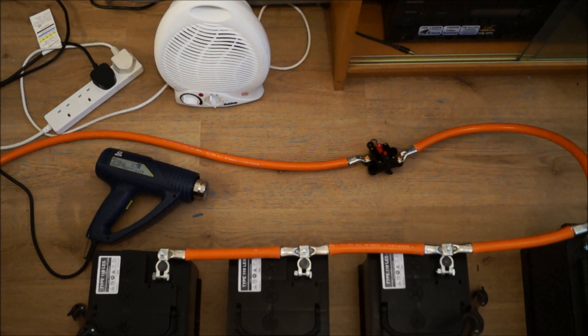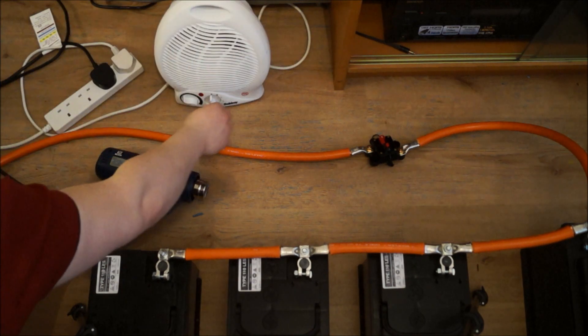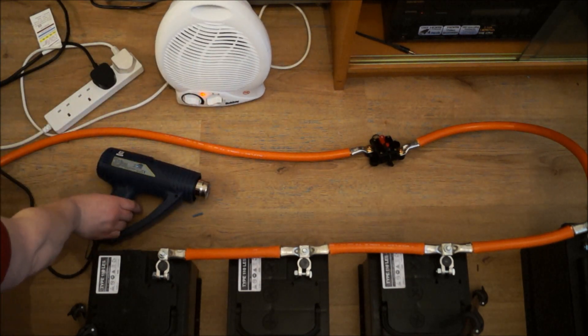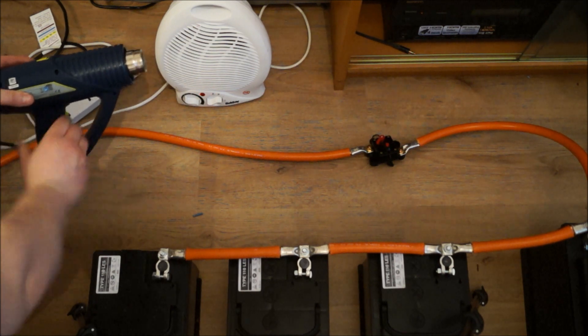So let's give this a go. Turn the inverter on. Inverter's on. Blow heater on. 4 kilowatts and it trips.